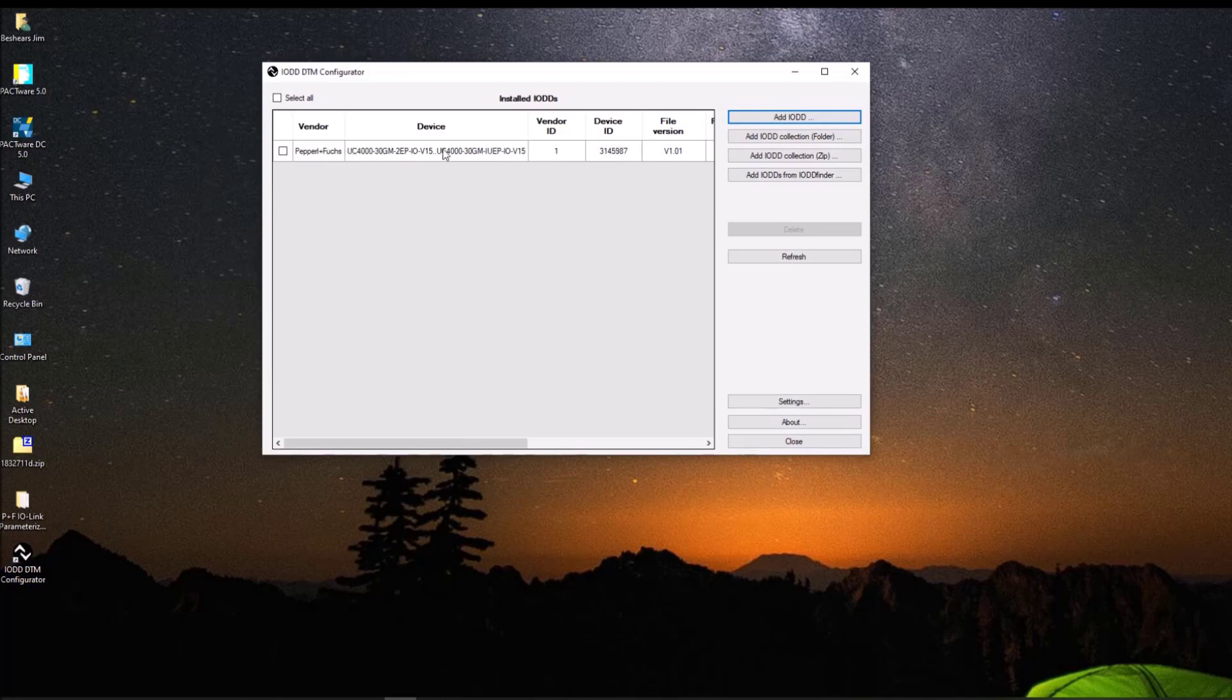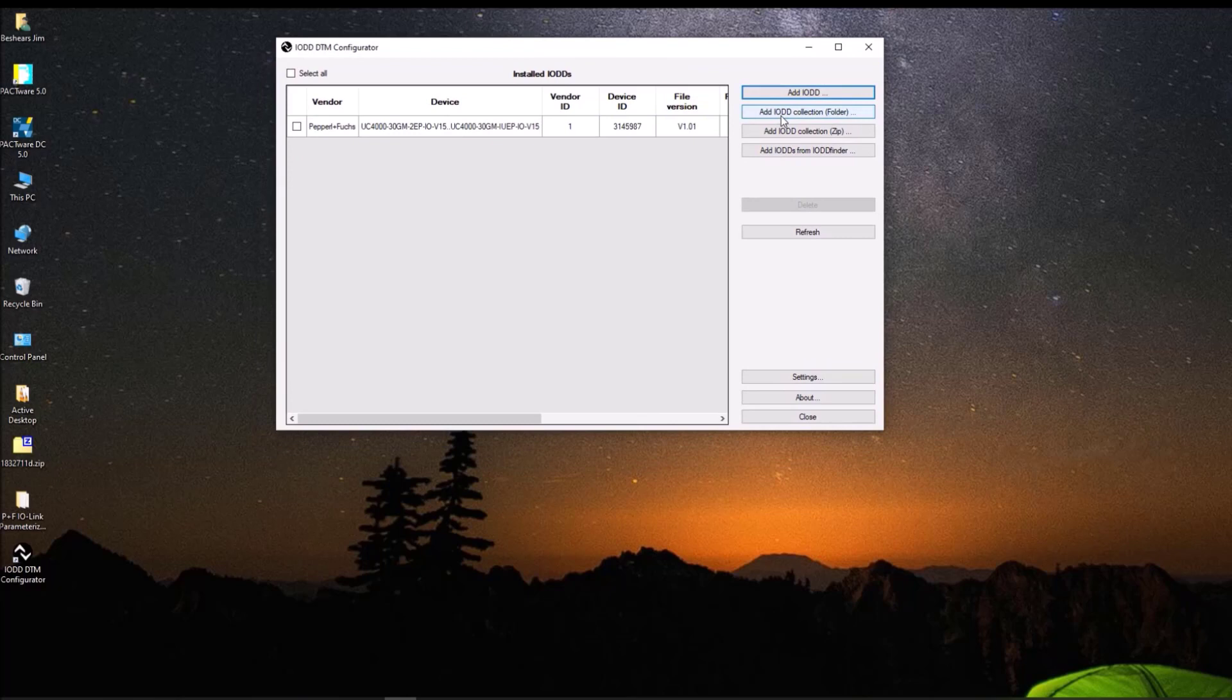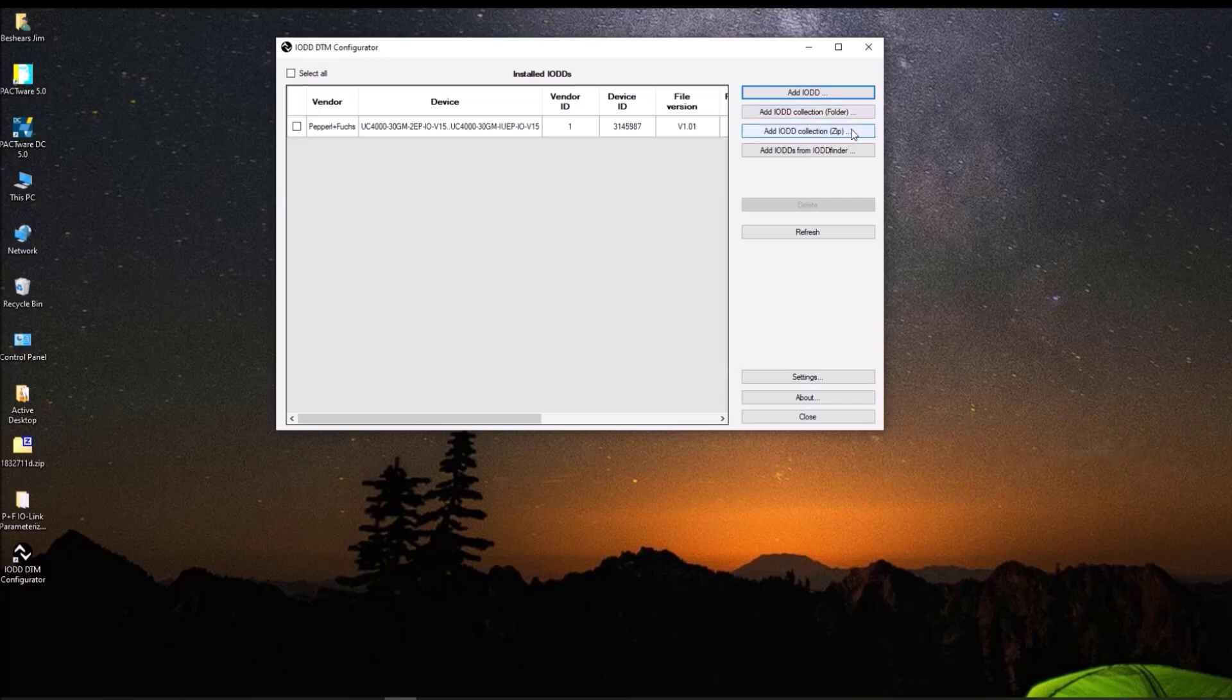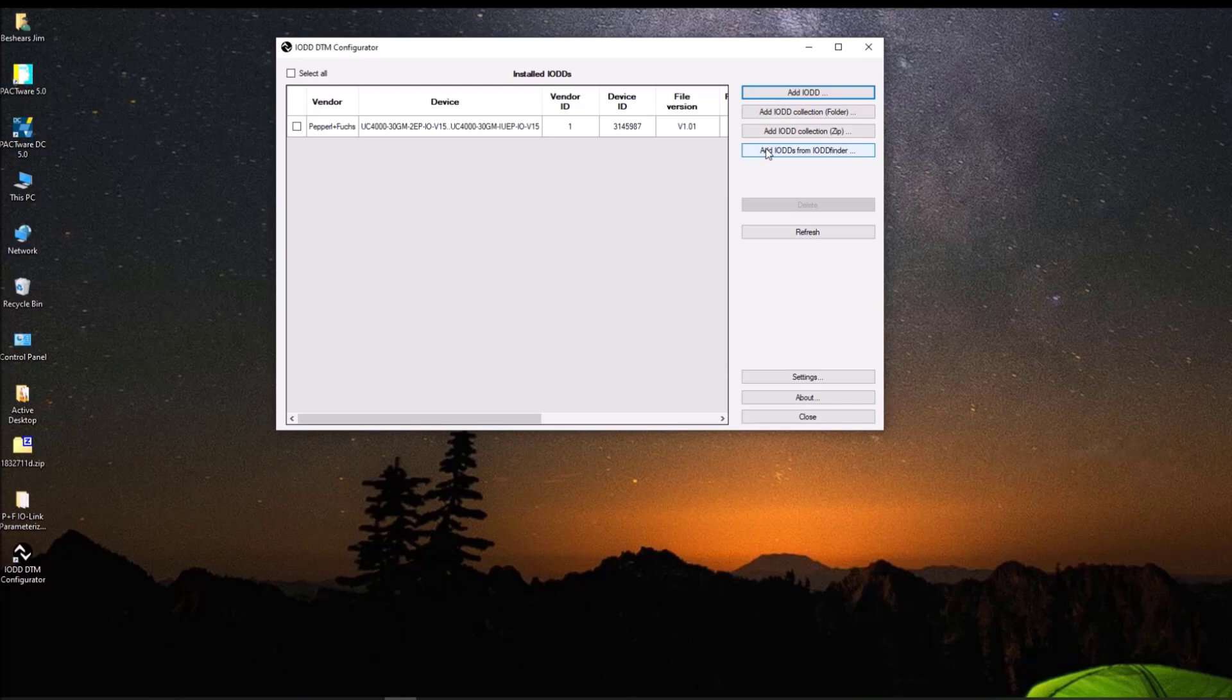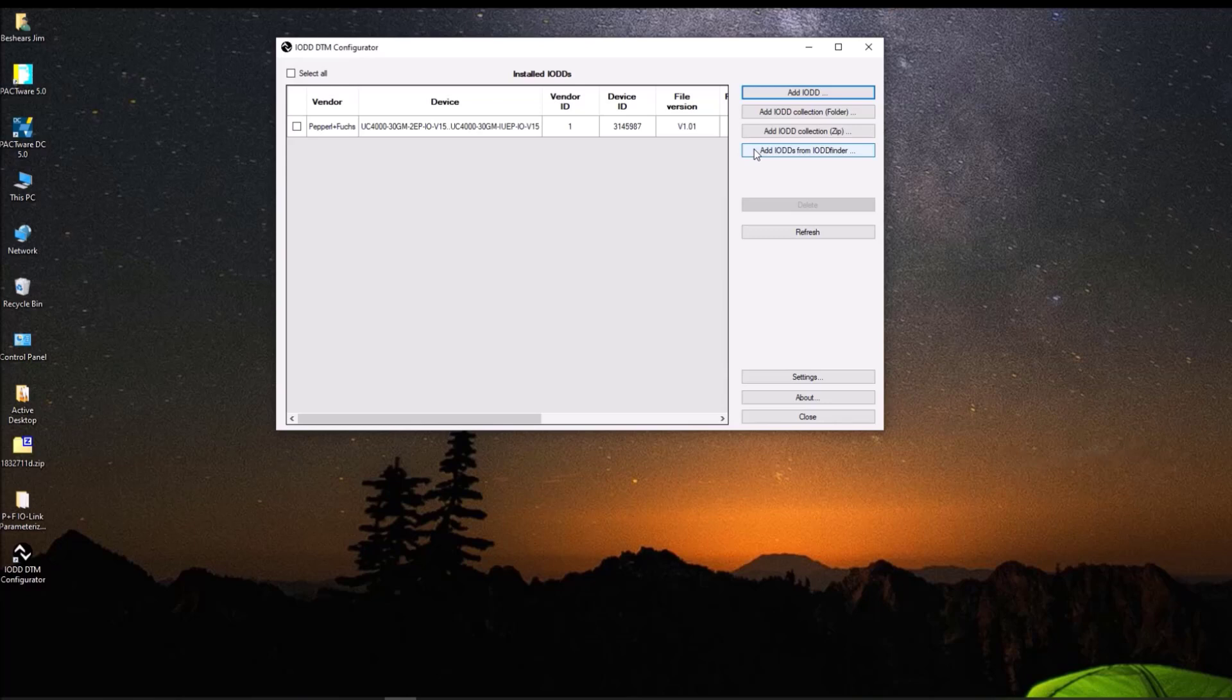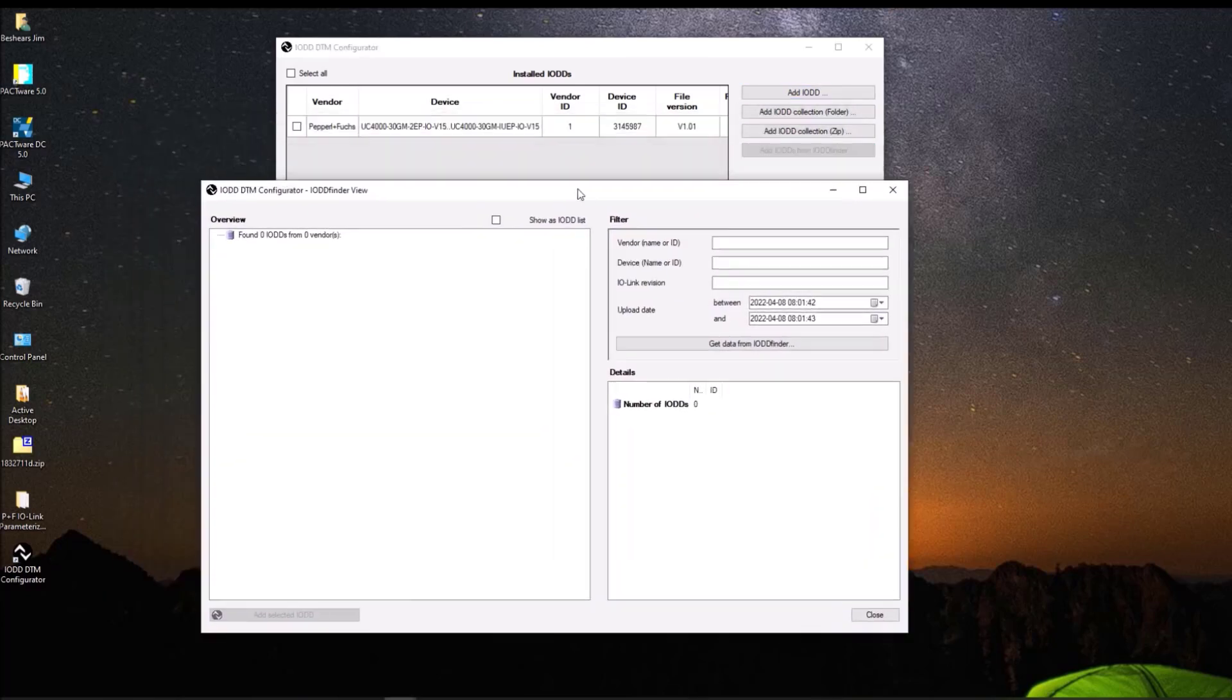So let's open the DTM configurator. And you can see here I have one for a UC 4000 already. And the way I got that, there's actually a few ways you can do it. If you have your IODD file in a folder, you can click on this and it will convert that into a DTM. If you have a zip file with a lot of IODD files in it, you can compile them all at once with this button here. And if you want to, if you're out in the field or at your desk or whatever, and you want to go and you don't know where to get these, you can go to a website called ioddfinder.com. And it will automatically find the IODD file for the device that you want to operate and download it to your computer. So that being the easiest and most up to date, let's look for that.